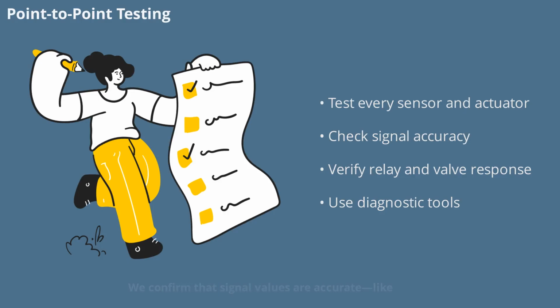Next comes point-to-point testing, where every sensor, actuator, and I/O point is verified individually. We confirm that signal values are accurate, like ensuring a 0-10V signal truly represents 0-100%. Relays, valves, and fans are tested for proper response, using tools like multimeters or diagnostic software. This meticulous process ensures that each component communicates and functions as expected.